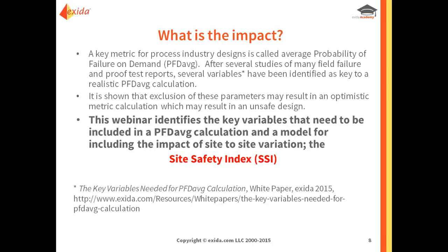Let's get back on topic though. It is shown that the exclusion of these parameters may result in an optimistic metric calculation, which may result in an unsafe design. That's very important to know, because a lot of people don't think about the other variables associated when you want to calculate an accurate PFD average. This webinar identifies the key variables that need to be included in this PFD average calculation, and a model for including the impact of site-to-site variations.